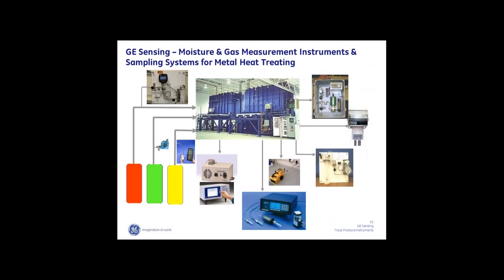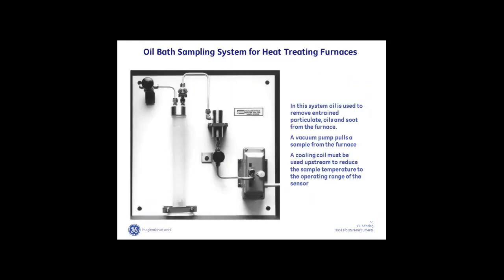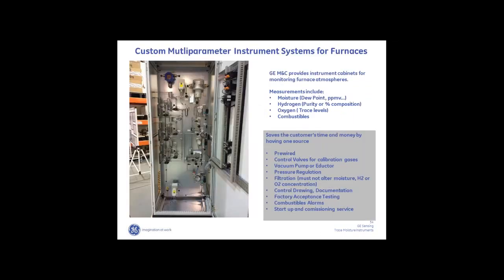In metal heat treating, you're creating atmospheres to impart certain properties into the metal — we measure both the feed gases going into the furnace and the furnace atmospheres themselves. Those atmospheres are dirty environments with a lot of metallic particulates and sometimes acid gases, so a very elaborate sampling system is required. One of the most effective is an oil bath where we literally bubble the sample through a container of oil — 5W30 motor oil. Just like motor oil in a car, it traps particulate material and becomes darker over time; eventually you change the oil. Here's a panel of that system with a moisture, oxygen, and hydrogen monitor all in one turnkey sampling system.